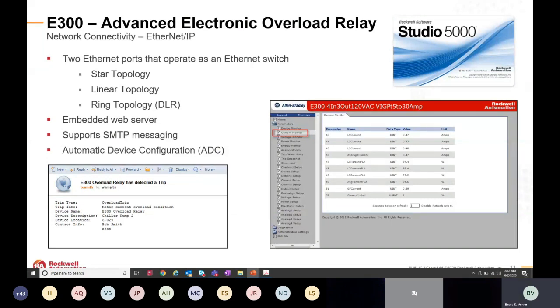And then if you're familiar with Rockwell's other Ethernet components that support a feature called automatic device configuration, that is also supported by the E300. So what automatic device configuration is: once you have a device configured and connected to a Rockwell PLC, the PLC will take care of archiving those parameters for the device, and in the event the device needs replacement, once you replace the device and set the IP address to the same as the device that you just replaced, the controller will take care of writing those parameters to the component itself. So that's why it's called automatic device configuration. It works with drives, static switches, and a number of other different PLC type communication accessories as well.